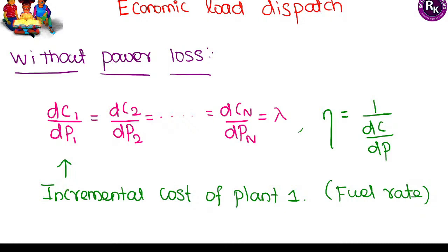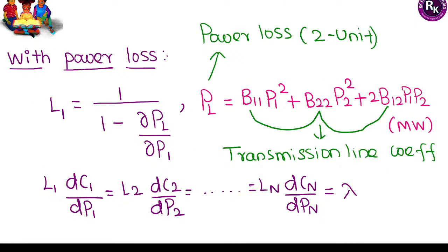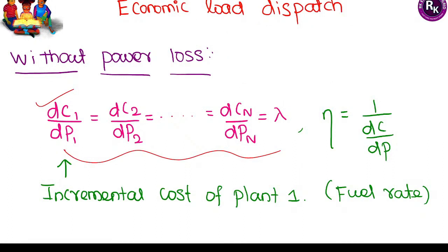Economic load dispatch is another important topic. Without power loss, the incremental cost of fuel — the formula to remember — must become equal for each and every power plant. That is the condition: incremental cost of each and every plant should become equal without power loss. With power loss, we also consider the penalty factor. The product of penalty factor and incremental cost must be equal for all plants.